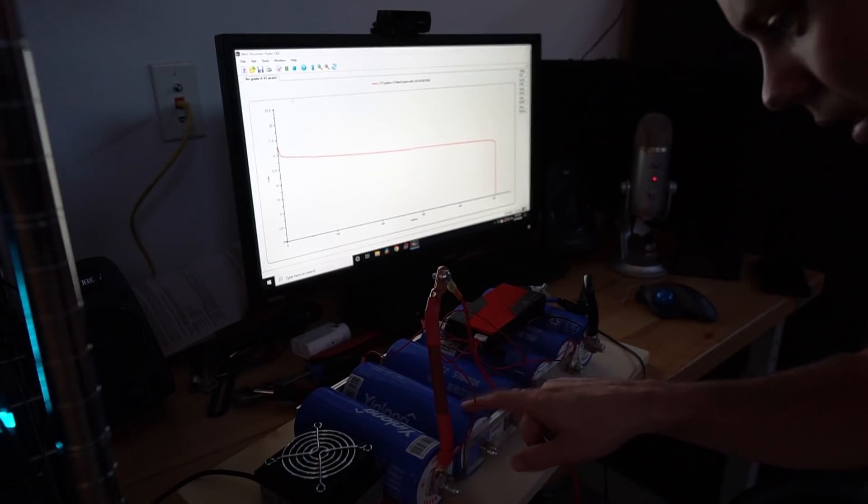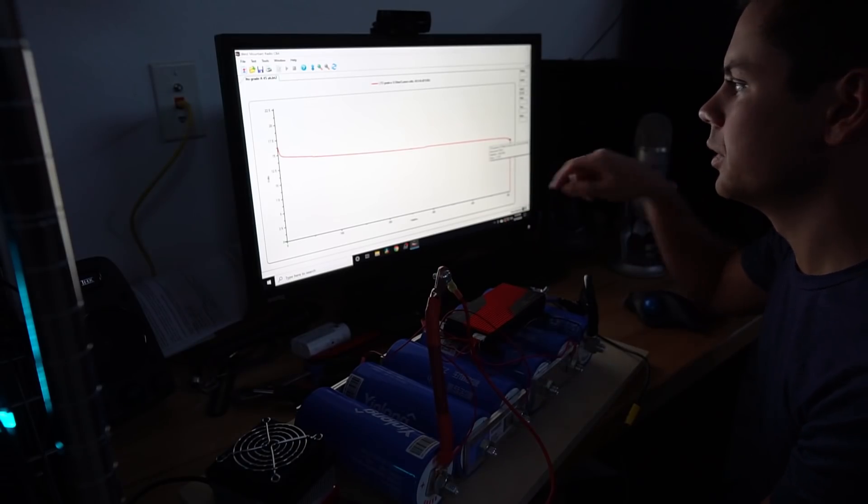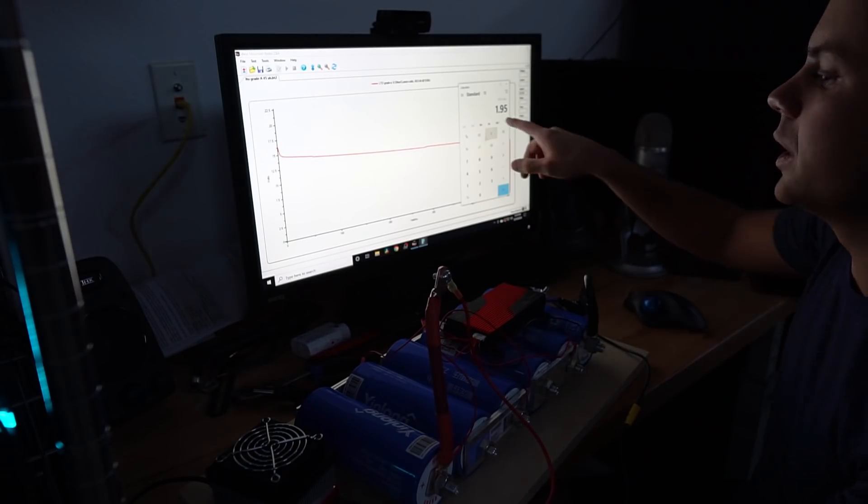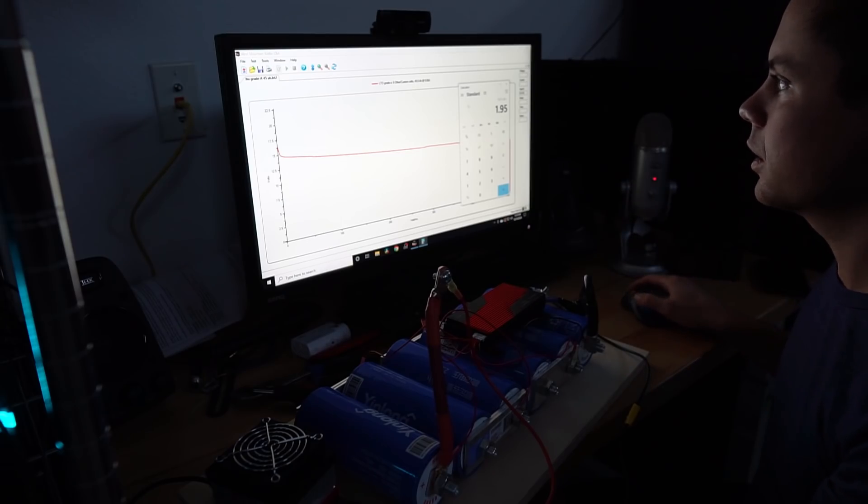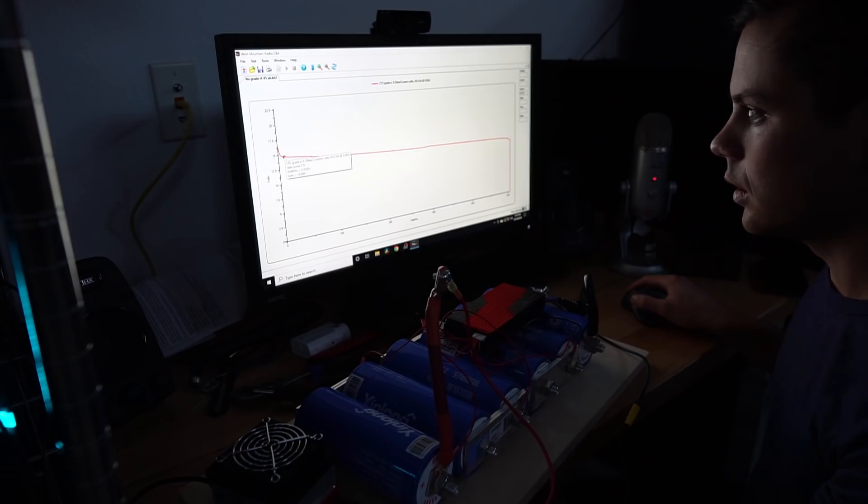The voltage dropped off at 11.7 volts, which is 1.95 volts per cell. So I think this is actually an accurate test. That's not good.